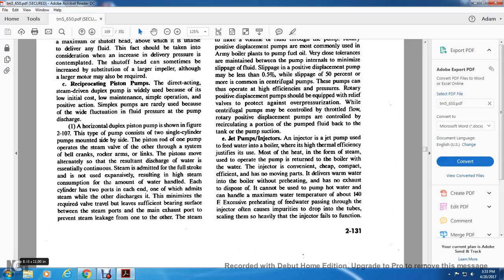This type of pump consists of two single cylinder pumps mounted side by side. The piston rod of one pump actually operates the steam valve of the other through bell cranks and rocker arm links. The pistons move alternately so that the resultant discharge of water is essentially continuous. The steam admits with the full stroke, not economically, resulting in high steam consumption for the amount of water handled.